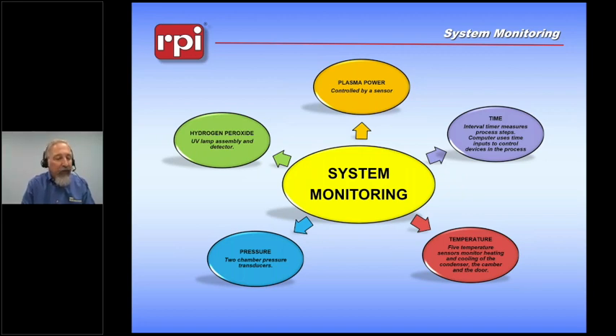There are 5 temperature sensors that look at the internal temperature in various parts of the machine, since we have to very carefully control the temperature to make sure that we keep the hydrogen peroxide as a vapor and don't recondense it again. There are 2 sets of pressure transducers, one that looks at the vaporizer condenser assembly and one that looks at the chamber directly. And of course, there's a hydrogen peroxide monitor so we can be sure that we've delivered the hydrogen peroxide to the chamber in the correct concentration, and that concentration is monitored throughout the cycle.